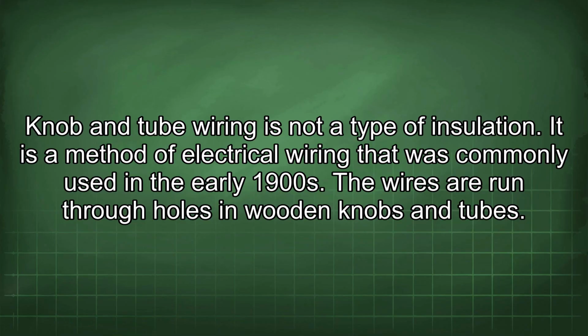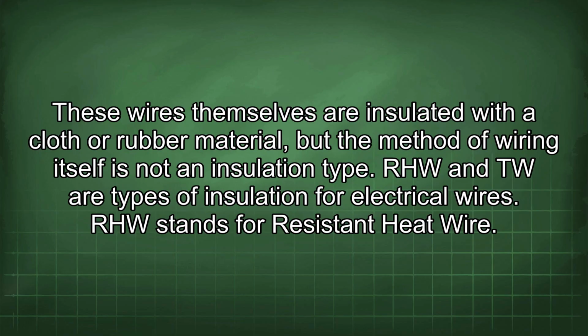Knob and tube wiring is not a type of insulation. It is a method of electrical wiring that was commonly used in the early 1900s. The wires are run through holes in wooden knobs and tubes. These wires themselves are insulated with a cloth or rubber material, but the method of wiring itself is not an insulation type. RHW and TW are types of insulation for electrical wires.